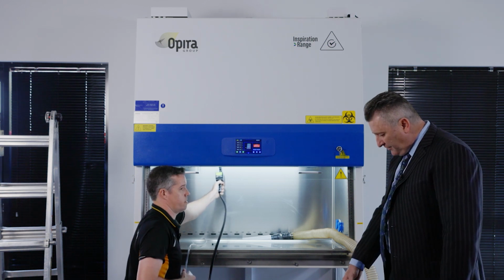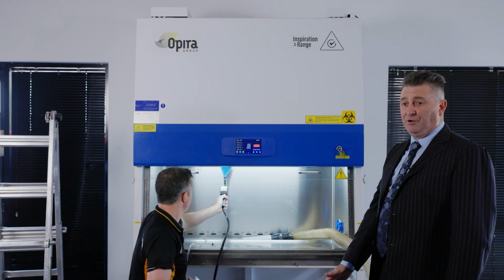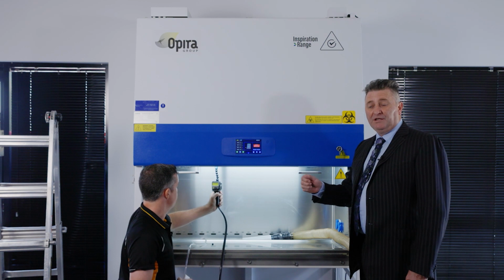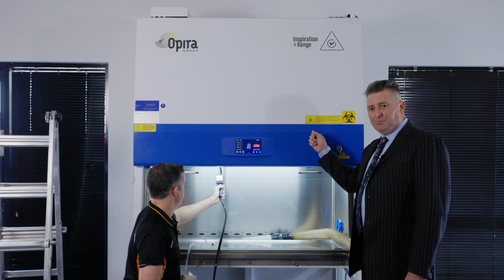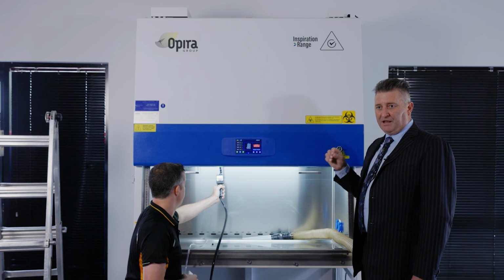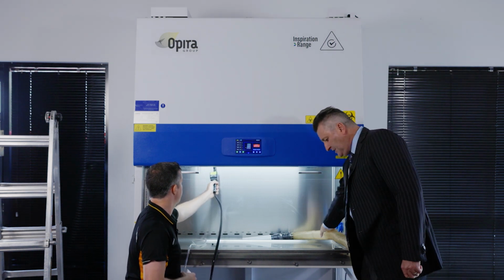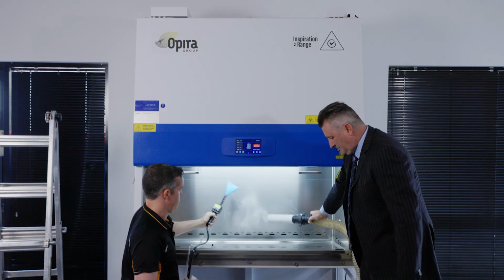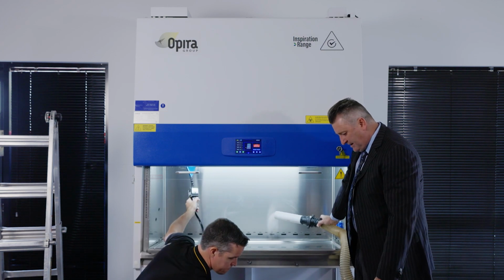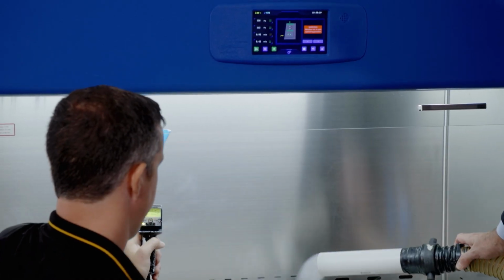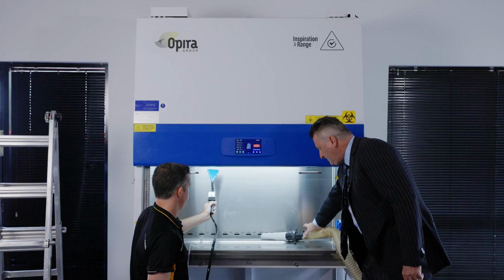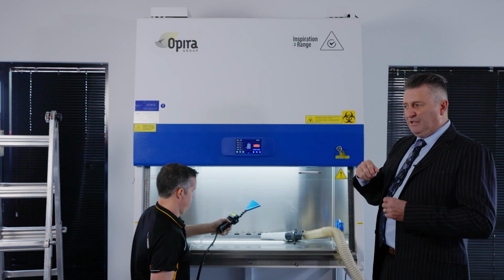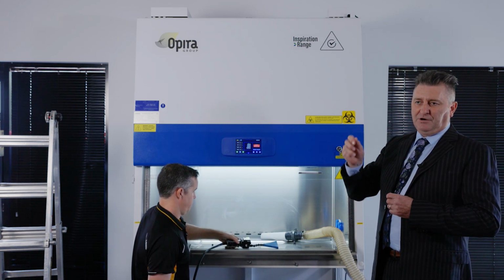So you can see here on the photometer it's reading 0, which means the filter isn't leaking. What Curtis is doing is scanning each of the pleats and the perimeter of the filter, making sure that there's no leaks. Just to give you an idea what happens when there's a leak, you can see the needle goes to 100%. So that's basically what it's doing. I guess that demonstrates the HEPA filter test. When there's a leak, there'll be an alarm and we'll see the needle increase.